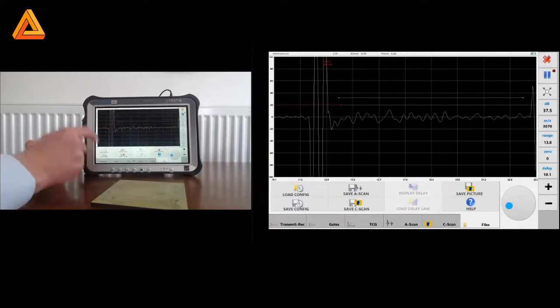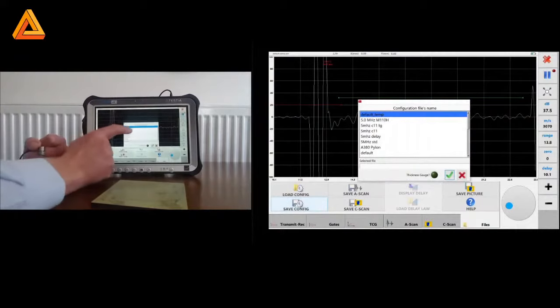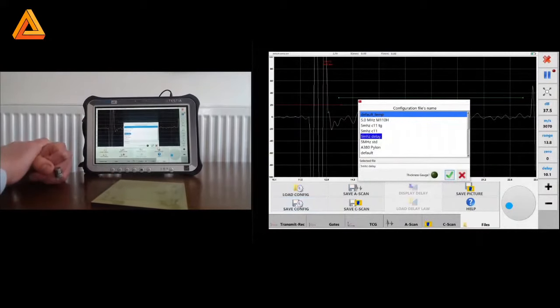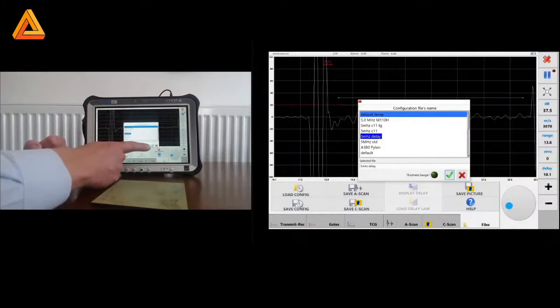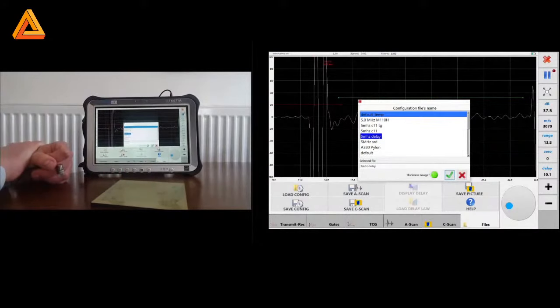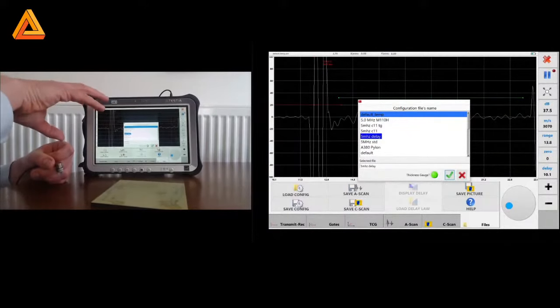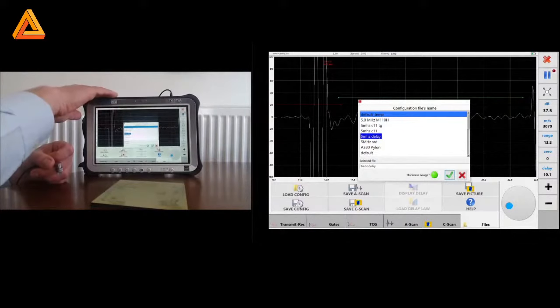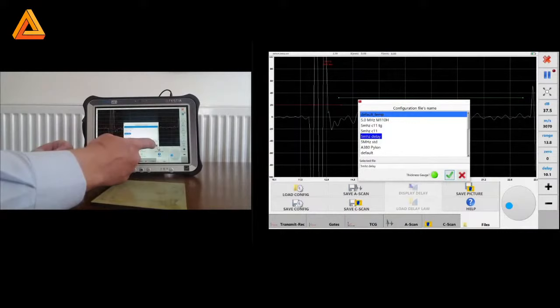So if we come to save configuration, this is my 5 megahertz delay line configuration, and along the bottom here we have a thickness gauge button. Now if we press that and illuminate the thickness gauge button, this will take the configuration we've saved in the flaw detector mode and transfer it into the thickness gauge mode.